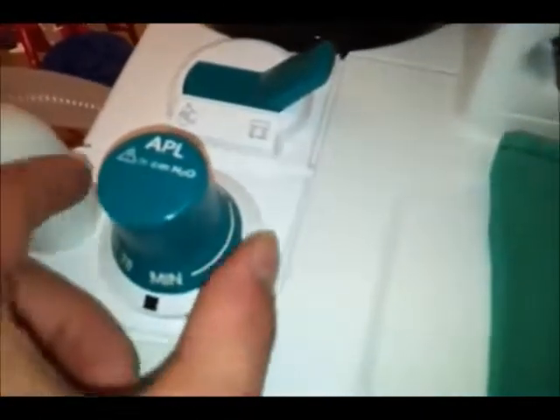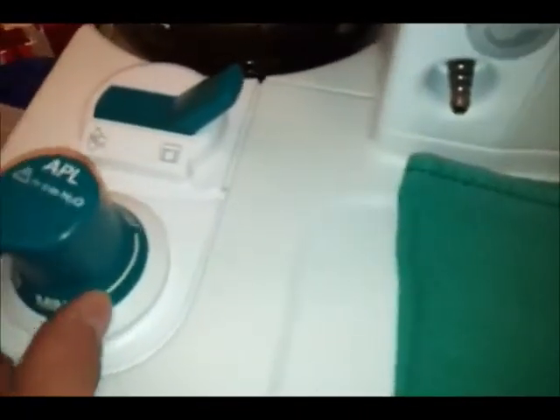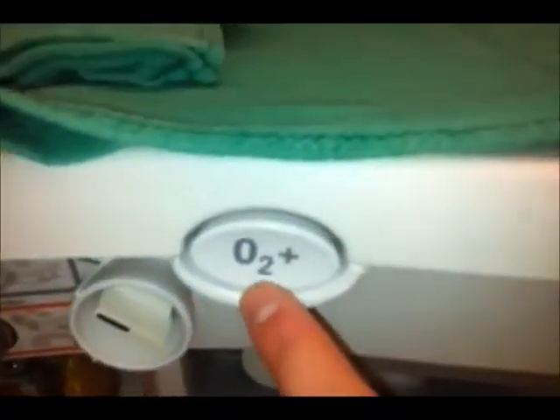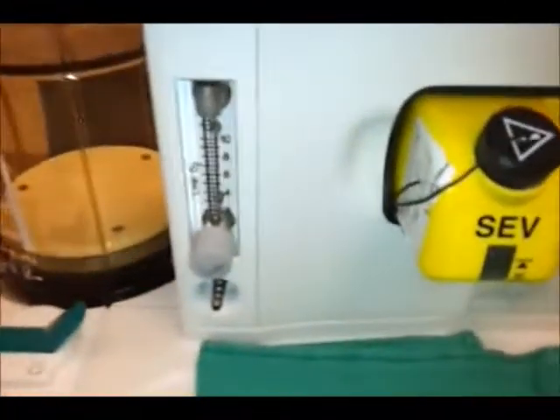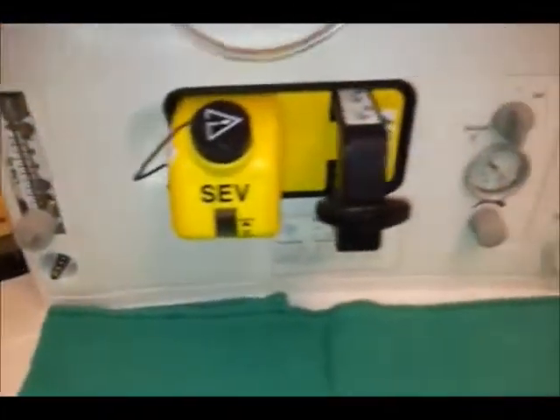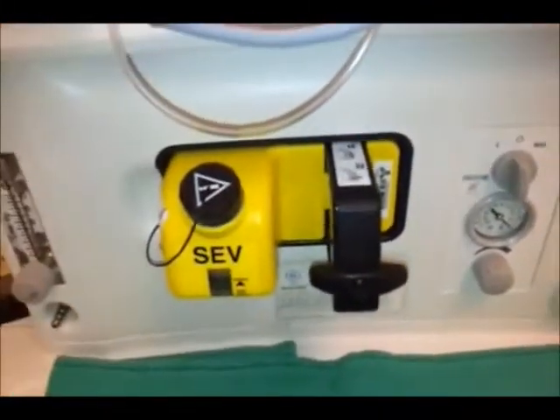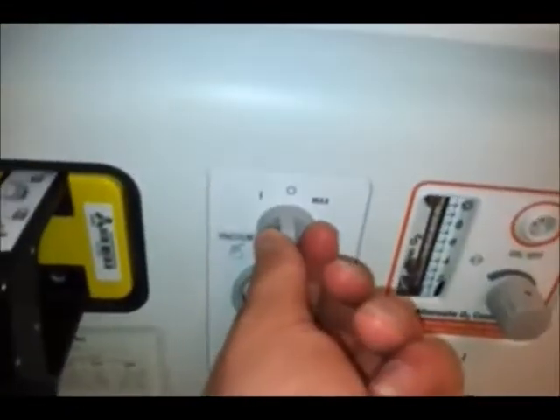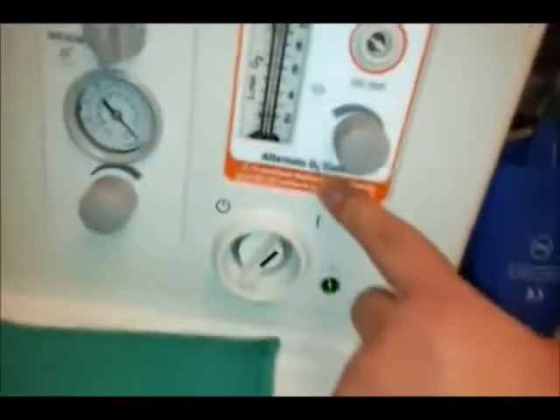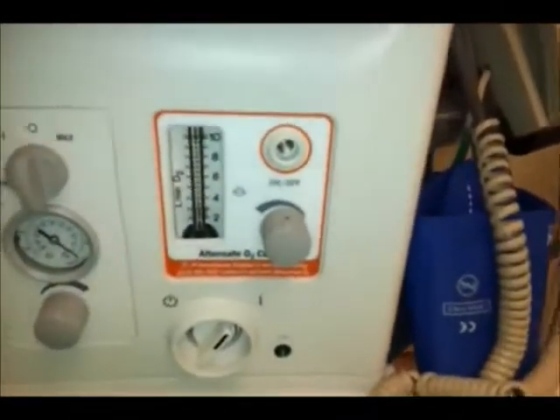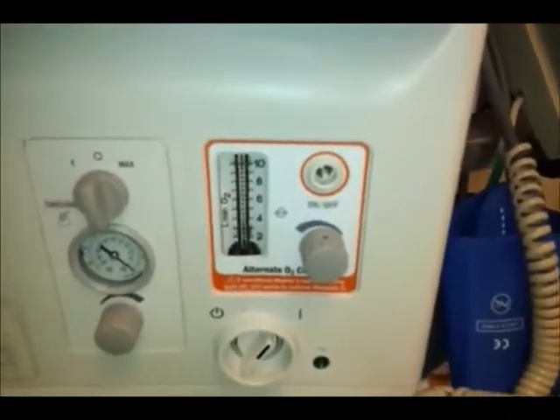Okay. So, there's the bag and vent switch, which I already showed you. The APL valve is right here. For the most part, it's set to min, unless you're going to bag someone. There's the ACGO switch, set to circle. O2 flush valve, which we're going to show you later. So on the front, there's an extra flow meter in case you need the bag, the volatile gas that's set up. Your suction supplies are right here, and your alternate O2 control is right there. You pretty much never use that unless the blender fails.